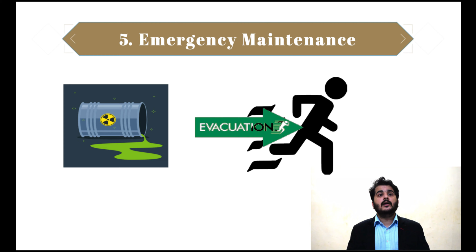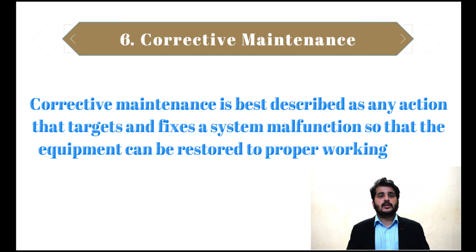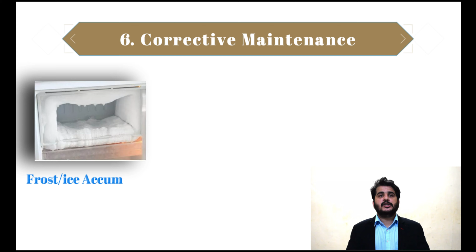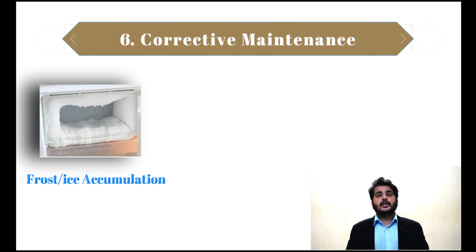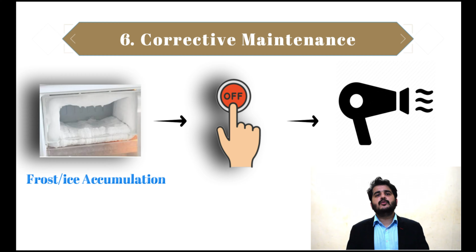appropriate authority. Last but not the least, the sixth type of maintenance is corrective maintenance. Corrective maintenance is best described as any action that targets and fixes a system malfunction so that equipment can be restored to a proper working condition. Example of corrective maintenance: if frost or ice accumulation happens, it can interfere with optimal refrigeration, causing compressors to run less efficiently.